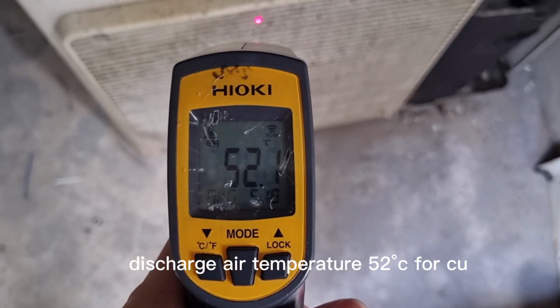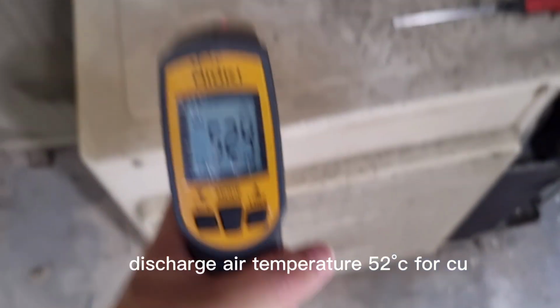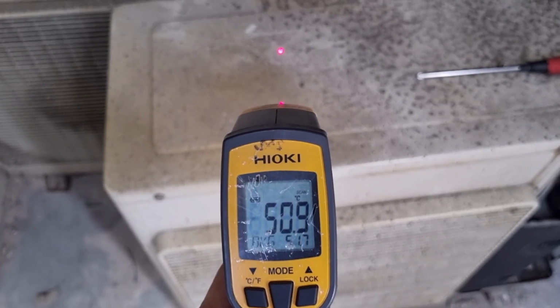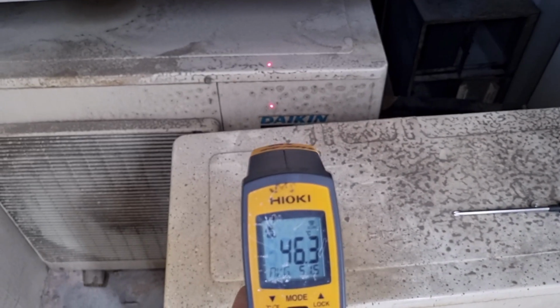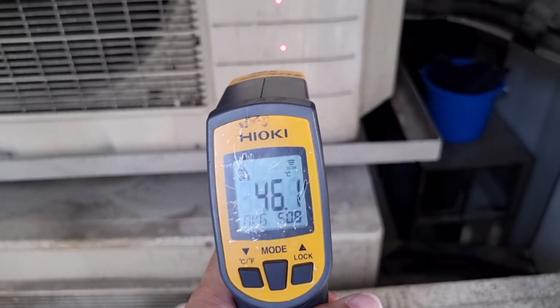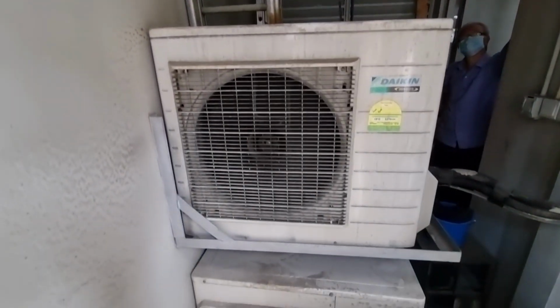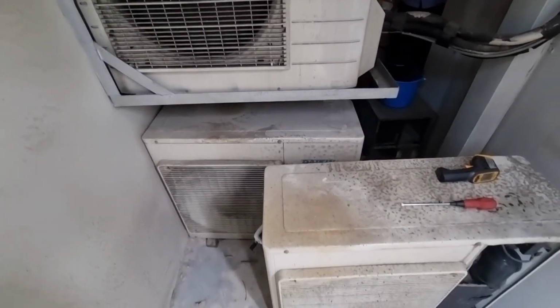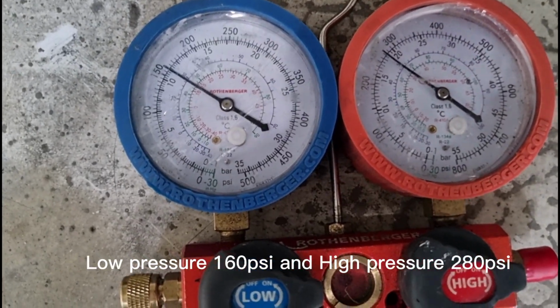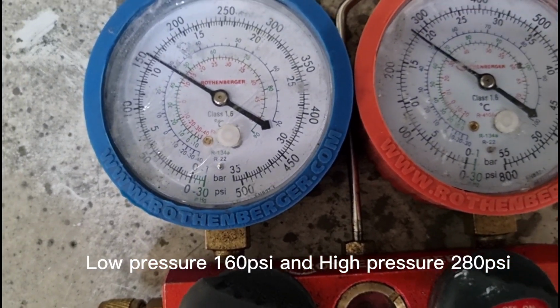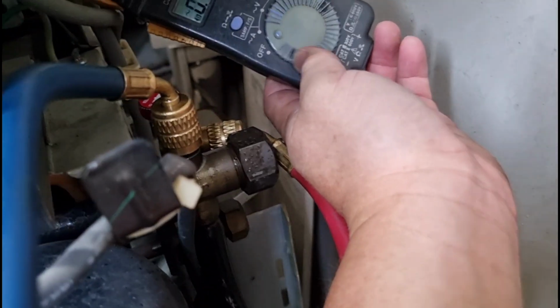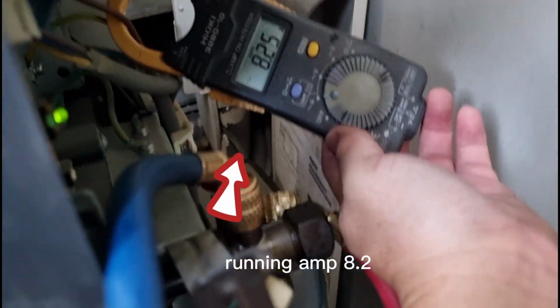Discharge air temperature of the condensing unit: 52.1. Okay, condensing body: 50.9. Low pressure 160, high pressure 280. Running amp 8.2.